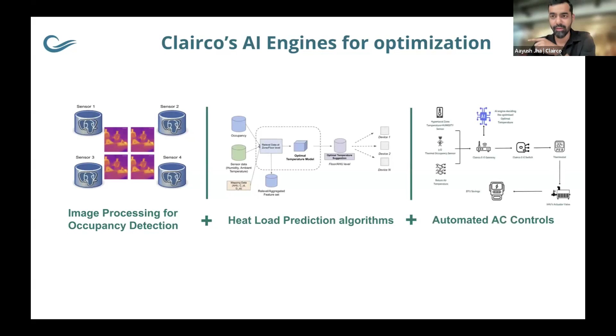First is the occupancy detection bit I told you about. Second, after we understand the occupancy-based heat load, we look at the ambient heat load — how sunny is it, is it going to rain, what ambient conditions help decide in real time what tonnage of cooling is required for that floor. Based on these readings and the BTU or tonnage required, we can control the low side of the HVAC, of chillers, in a large commercial building, to help save energy.